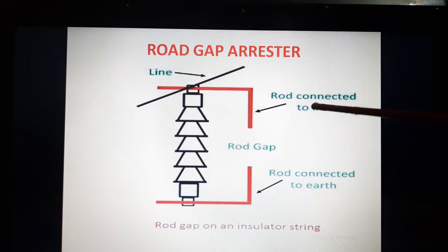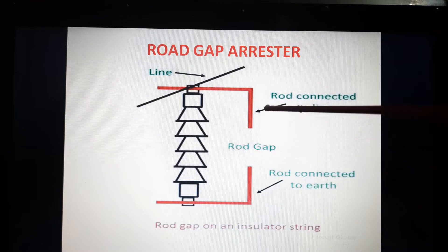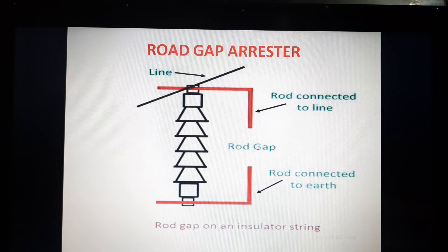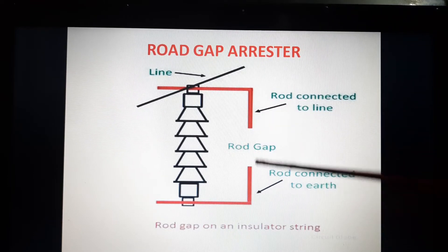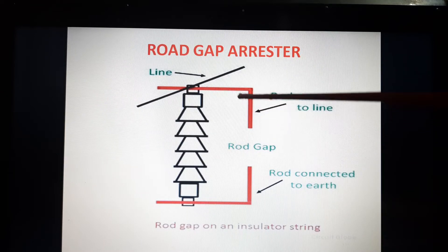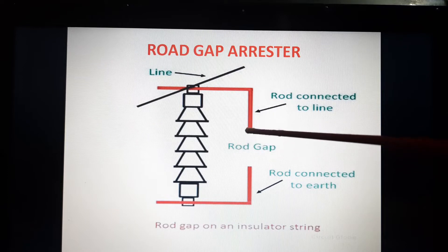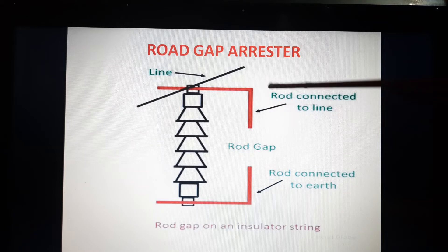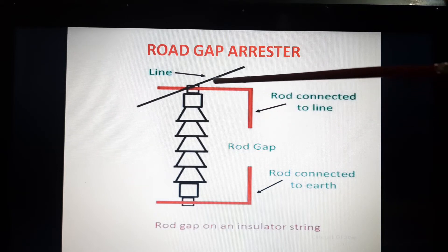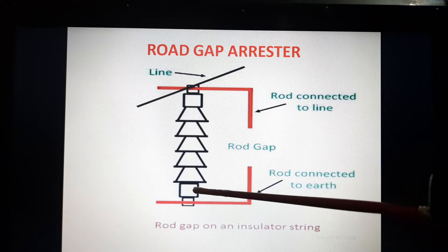This is the figure of the rod gap arrestor, which is connected across the bushing of the transformer. It is the simplest form of arrestor. It consists of two rods — 1.5 centimeter diameter rods which are bent at right angles with a gap in between them, as shown in the figure. One rod is connected to the line and another rod is connected to the earth.